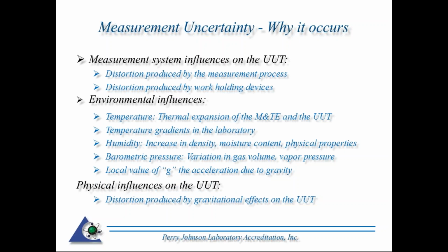So we have measurement system influences on the UUT, and again, that's unit under test. So these are the artifacts that are being calibrated. You can have distortion produced by the measurement process. You can have distortion produced by work holding the device. Some devices are very sensitive to changes. I remember I was doing an assessment once and watching someone calibrate one of these devices. They were putting it down and holding it on their knee between readings, and I'm thinking to myself, well, that's definitely introducing a distortion of that device, heating up the element.